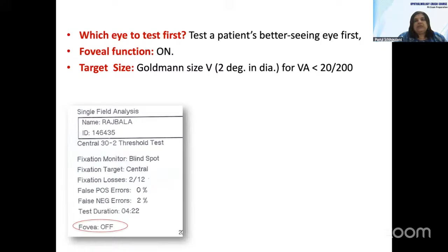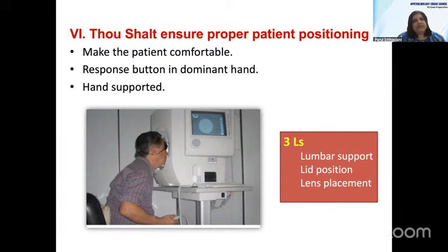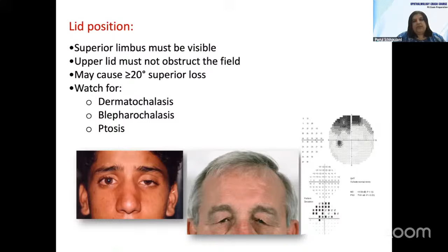Change the target size if the visual acuity is less than 20/200. Then you can step up to a Goldmann size 5 from Goldmann size 3. Always maintain proper patient positioning because that is going to give you a reliable result. The patient should be comfortable. The response button should be in the dominant hand and the hand of the patient should be supported. Always remember the 3 L's: lumbar support, a good lid position, and lens placement. The superior limbus must be visible when the patient is performing the test. The upper lid definitely must not obstruct the field. These days, we see a lot of elderly patients having dermatochalasis or lid issues secondary to prostaglandin-associated periorbitopathy, and all these lid issues ultimately result in a superior visual field loss. So that is something you can address by taping the lid of the patient.